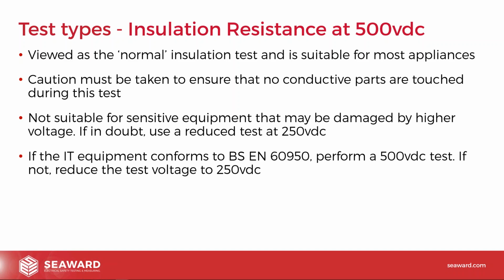And also IT equipment, as long as it complies with BS EN 60950, it should be okay to perform a 500 volts DC test. And again, if we're not sure, we've said reduce that down to 250. In theory, equipment that's tested to BS EN 60950 is flash tested in the factory when it's produced. So because it's flash tested at a very high voltage, the 500 volt DC test should be absolutely fine on that. The only caveat is just make sure it does actually comply with that standard, because if it's counterfeit equipment or if somebody's just put the standard on but they don't really test them properly in production, there is still a possibility you could damage that equipment. So again, go back to the advice before. If in doubt, go down to 250 volts DC.